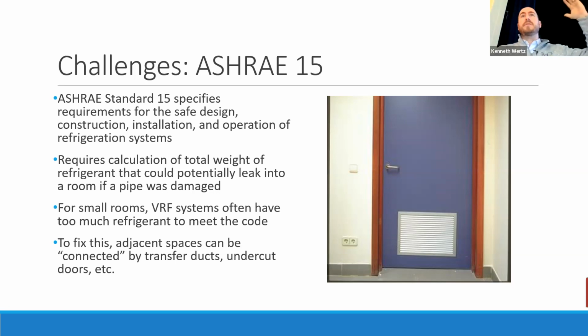You know, the oxygen would rise to the top, out of where people can breathe, and people could asphyxiate, could die. So there are codes, obviously, to prevent that from happening. In larger systems, you'll have to have a whole refrigerant leak detection system that people may be aware of from having chillers, that's sensing that and has an exhaust emergency that can get rid of that dangerous condition if it ever happens.